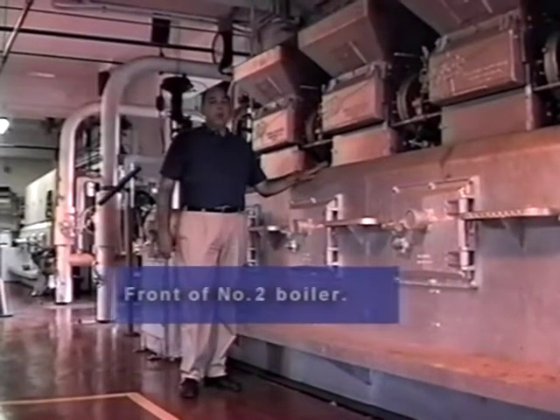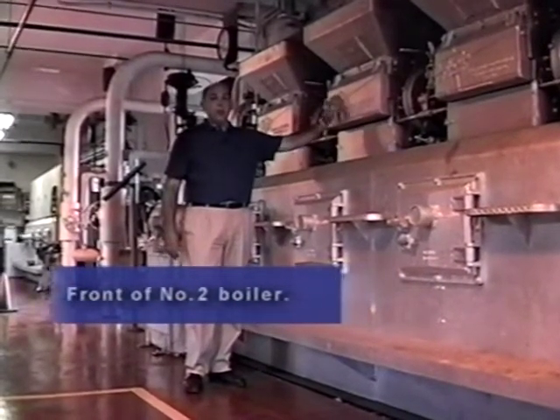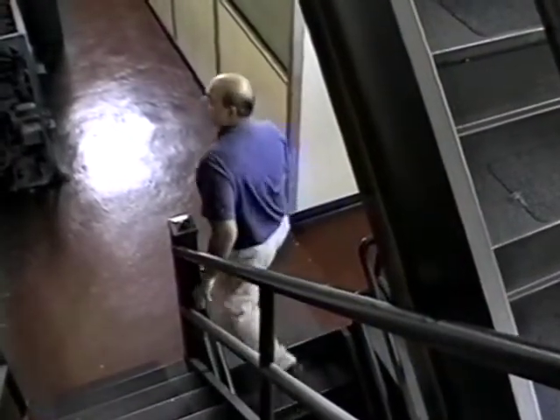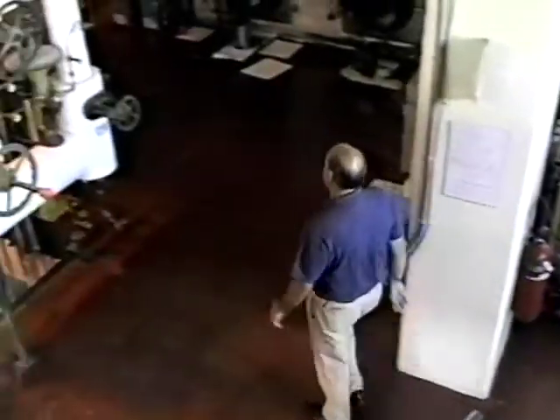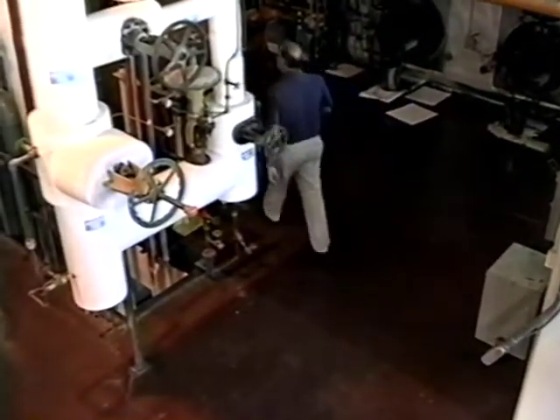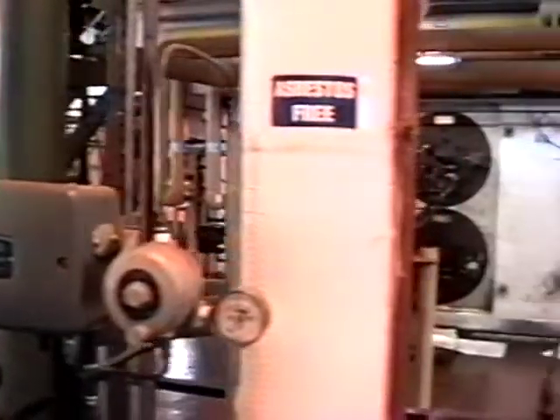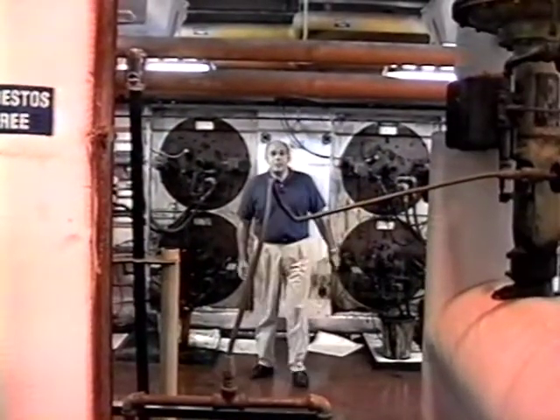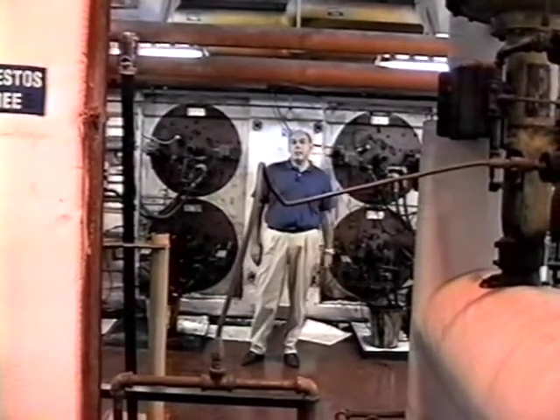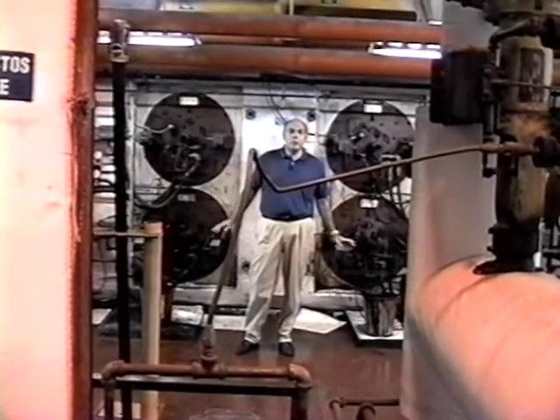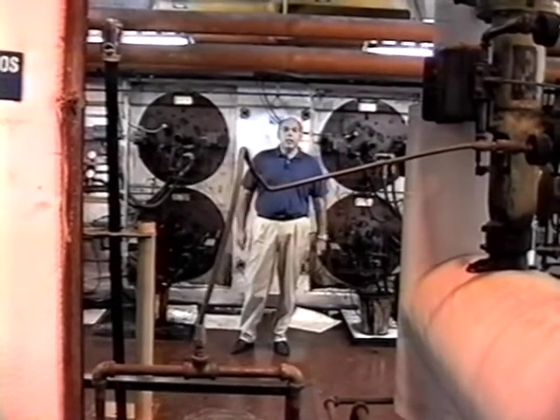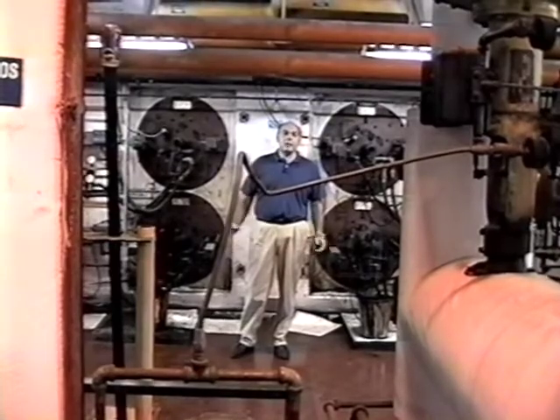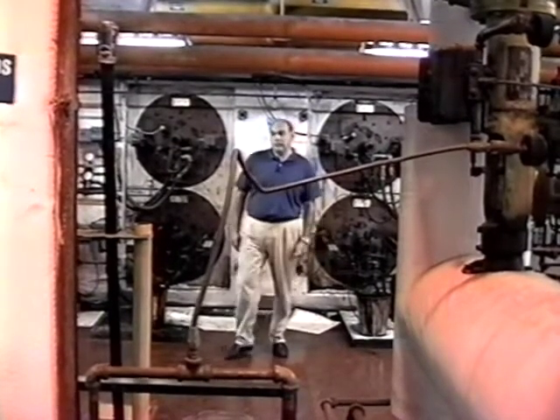This is the front of number two boiler. These are the old coal stokers that are no longer used. This is the burner front of number two boiler. Pier Station has three boilers. Each boiler has four burners, and we burn about 1,000 gallons per hour in each boiler.